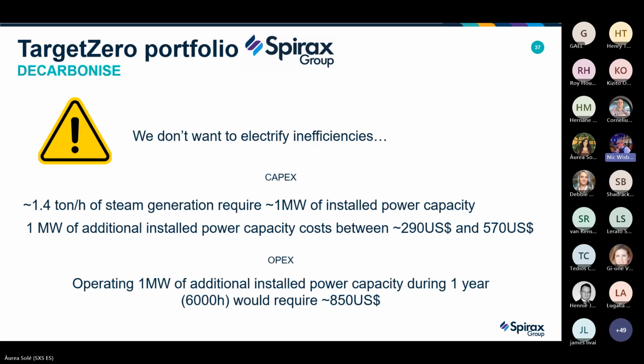That's why we want to make your system as efficient as possible. The less steam you're using, because you've rectified leaks and you're using what you have more efficiently, the smaller your electrification boilers can be, if that's the route you choose. I know East Africa, from my experience of being here for almost 2 years, it's mostly biomass. But even biomass is not green, it's not net zero unless you have a closed loop of supply fuel. So it needs to be renewable.